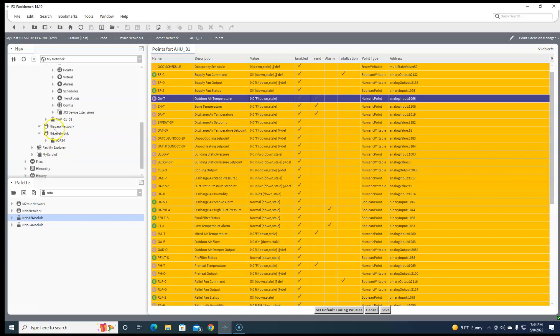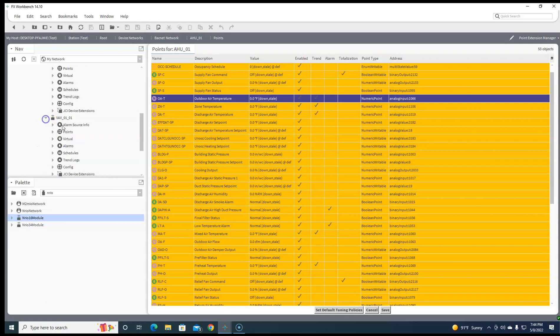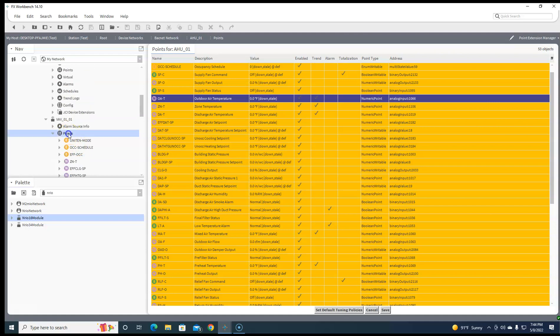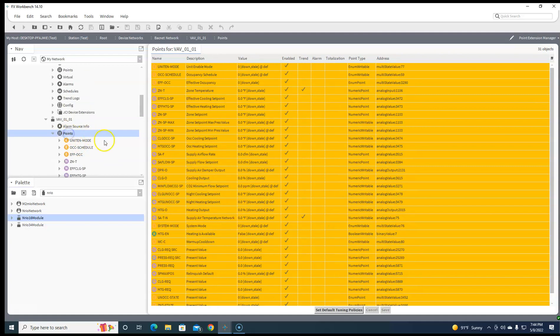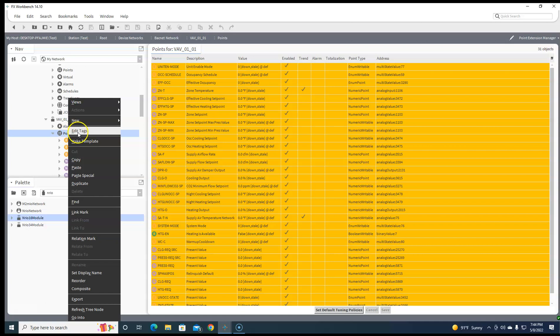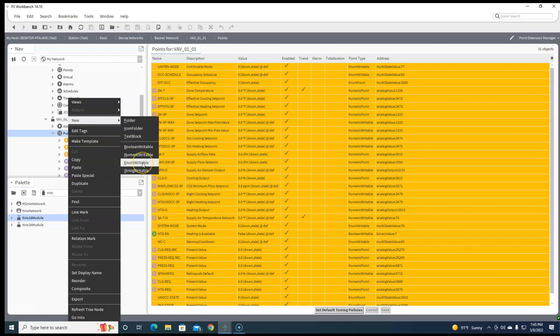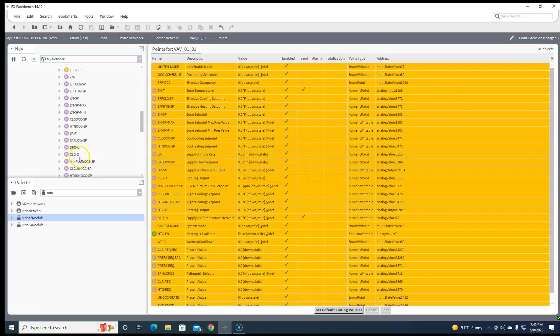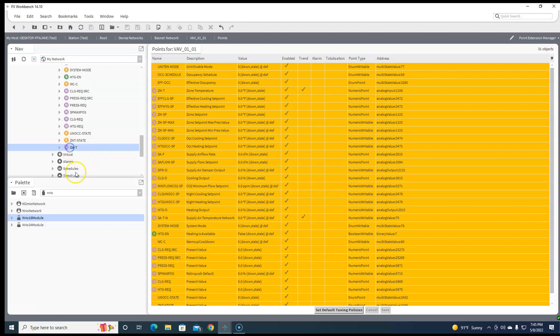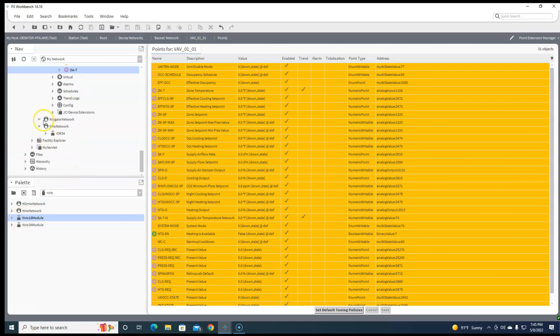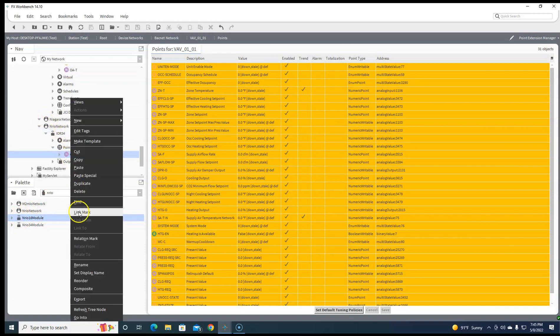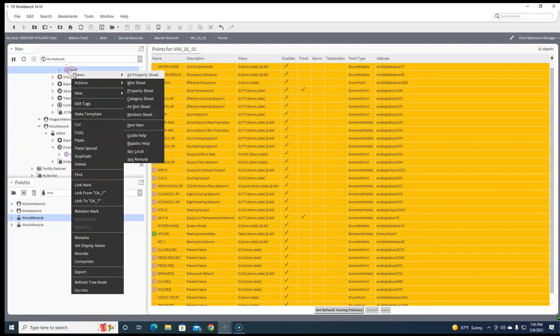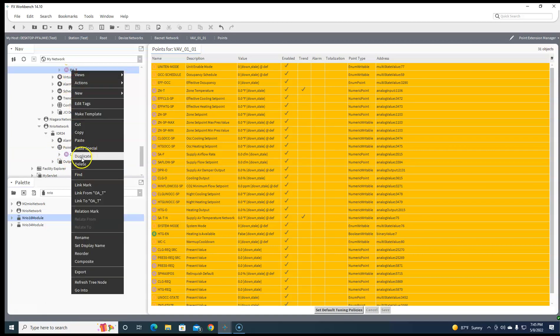But if we didn't have one, like maybe this VAV doesn't have one, we should be able to do a new numeric writable and call it OA-T, and then we should be able to link our IO 34 point to this guy.